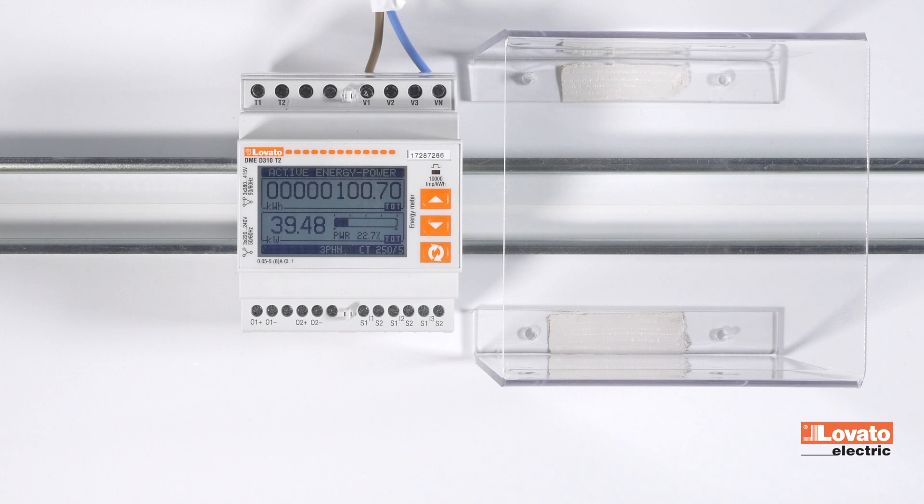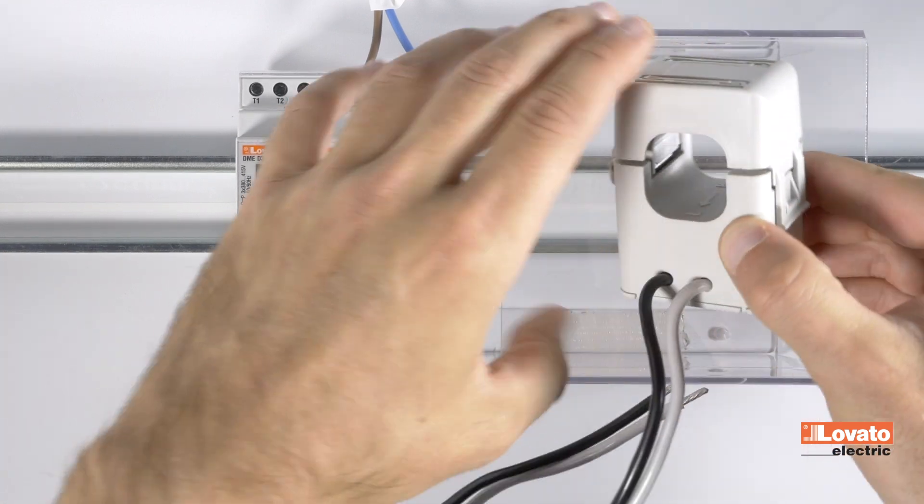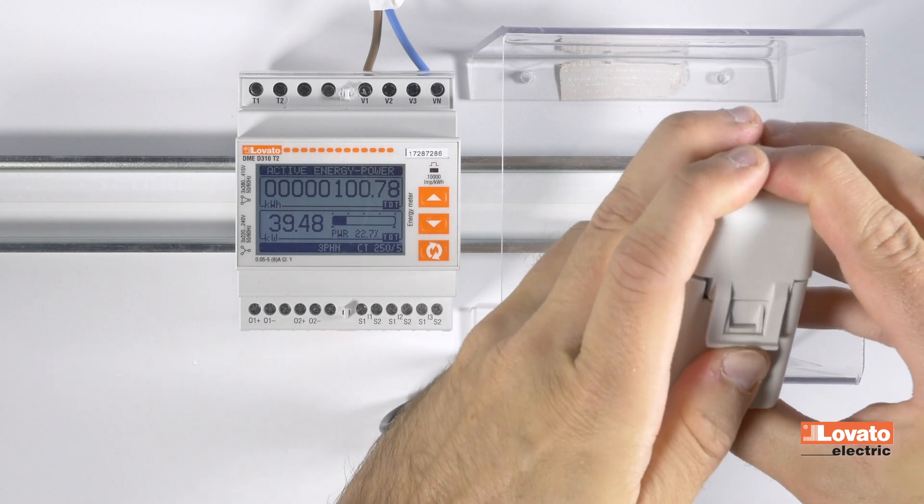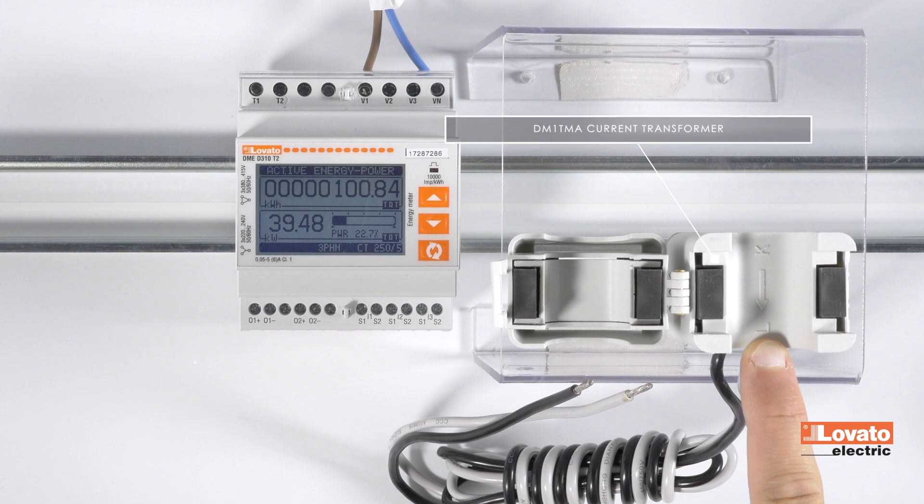To connect the openable compact pre-wired CT-DM1TMA at 250 amps, check the direction. The current has to enter from side K, visible here, and exit from side L, marked here.